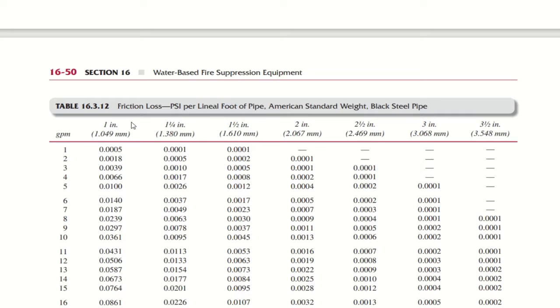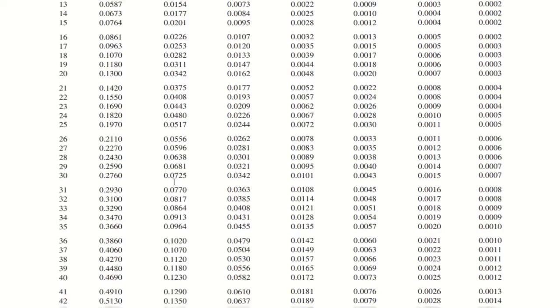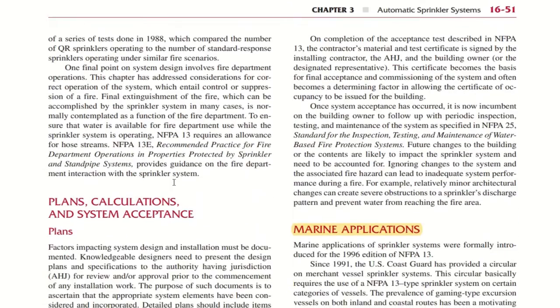Here we have one more table, friction loss psi per linear foot of pipe for black steel pipes. So for black steel pipe you have various sizes, and the friction losses are mentioned here based on the GPM. This is also an important table.